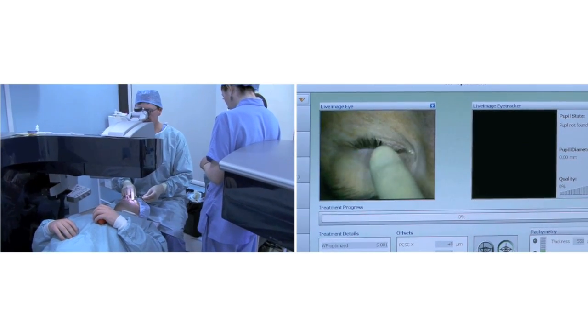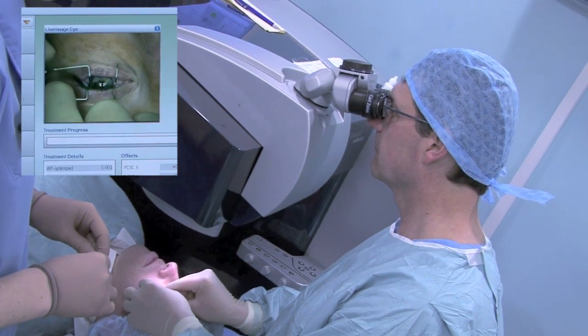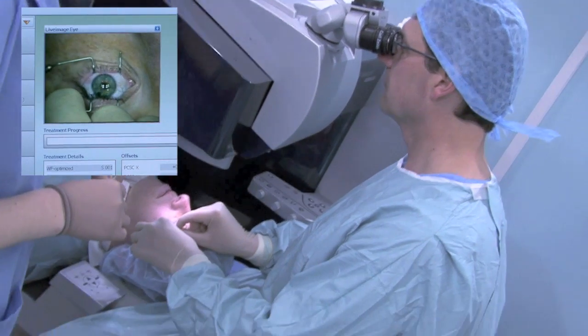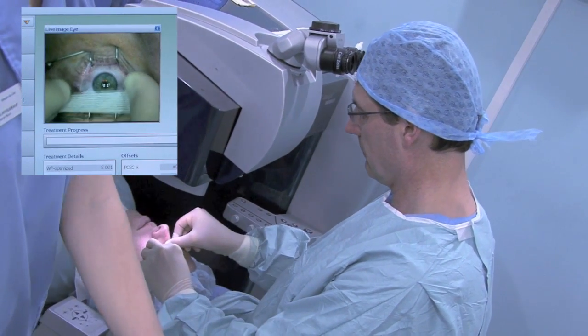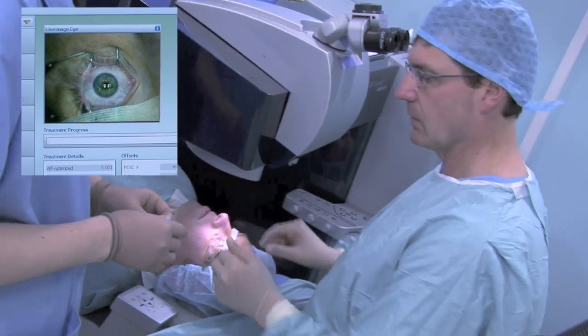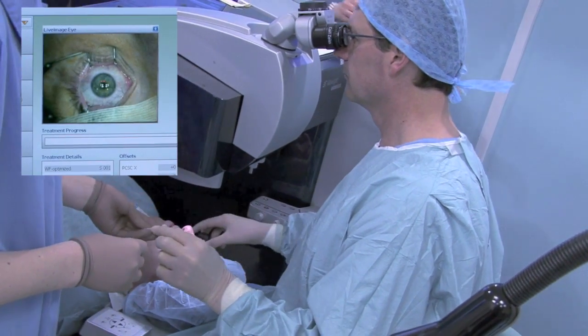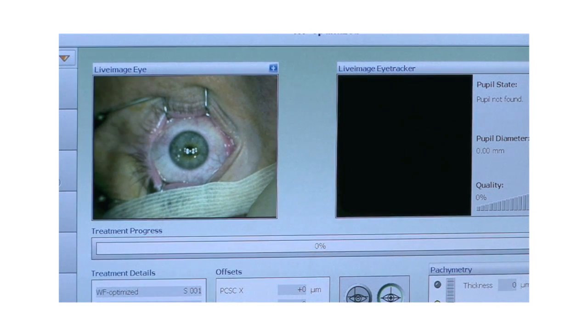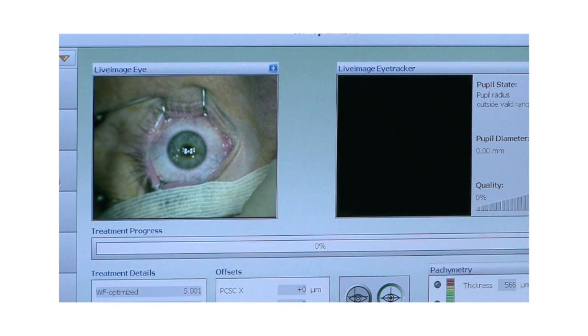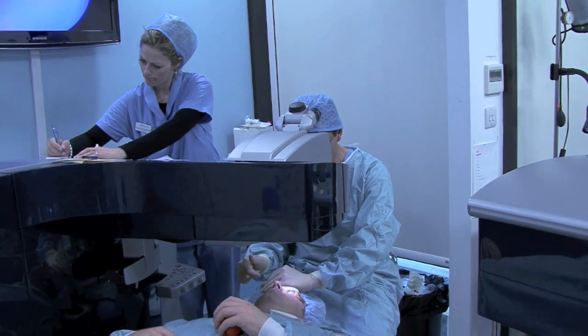Even though you know exactly what to expect, this still feels strange — just give it a minute getting used to this. The EX500 has increased working distance and there is more space for maneuvering. The motorized eye tracker does not swing into position as with the 400 IQ, but glides into position by dropping down gently and lifting up afterwards. We're now going to do another measurement. Non-touch pachymetry allows measurements of the preoperative corneal thickness and then, once the flap is made, the residual corneal thickness, providing very accurate measurements of flap thickness intraoperatively without any instrument touching the cornea.